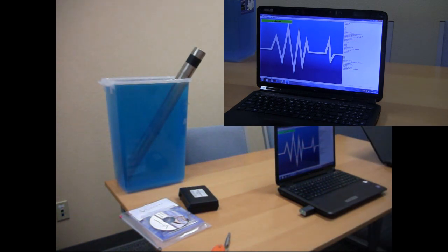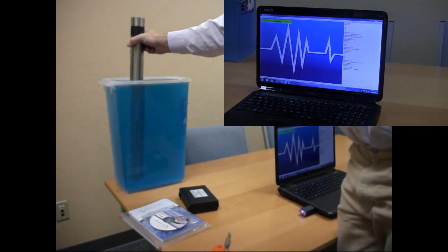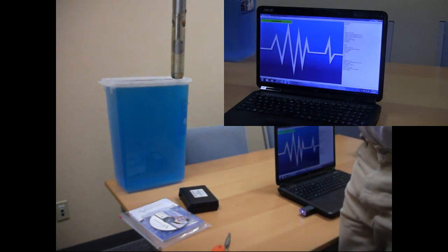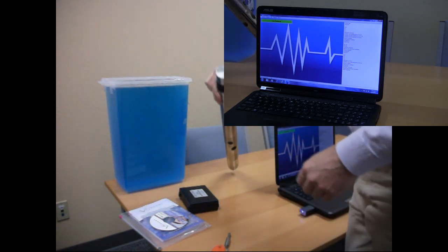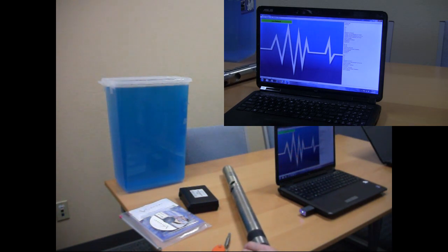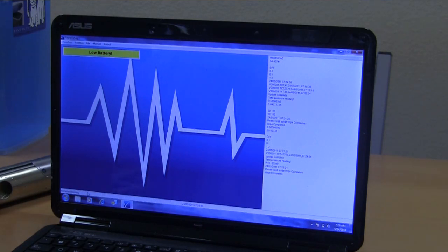Going to do a much shorter cast this time. So the instrument's running again. You'll see here that the Bluetooth connection has been severed because the probe's below 0.1 meters in depth. So what we're going to do is pull the probe out and simulate a much shorter cast. So the probe's coming back already. Okay, so the probe's out of the water. Unlike last time, the data will not be automatically extracted because we haven't reached the 2-minute period. So in 60 seconds, the first communication with the probe will be established, and then that data will be extracted.